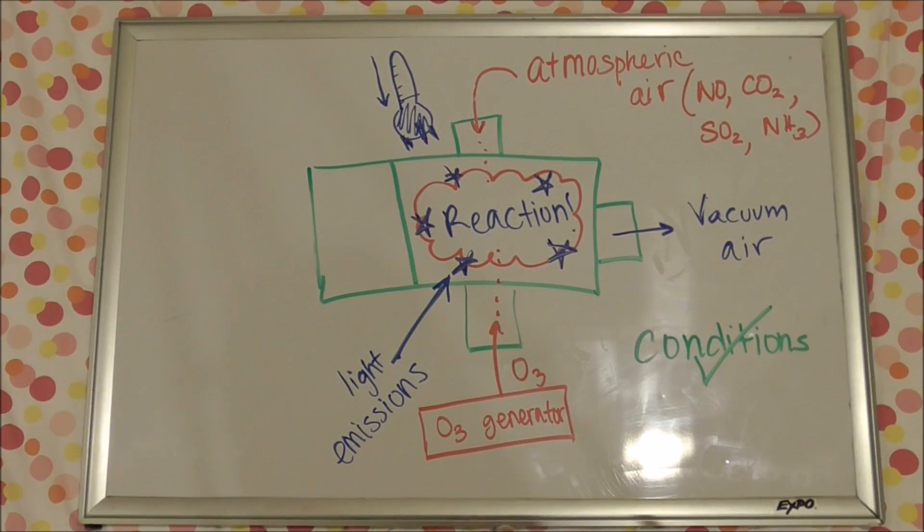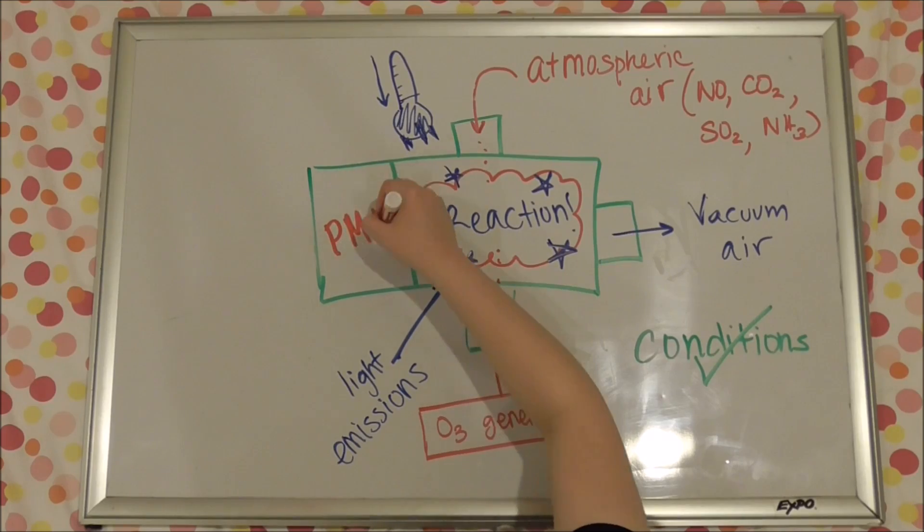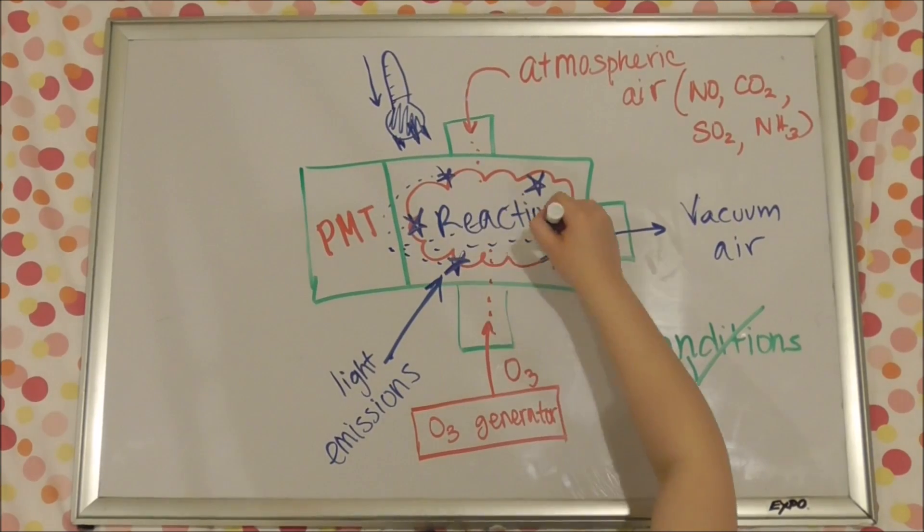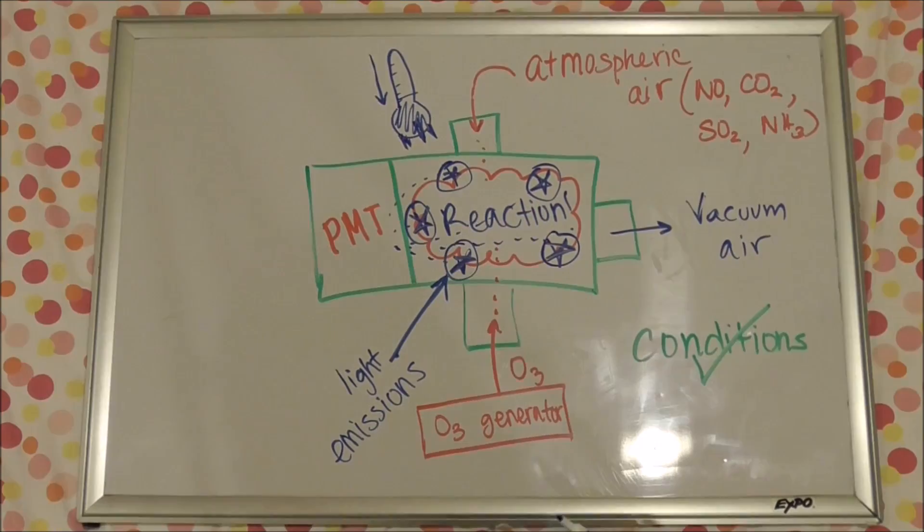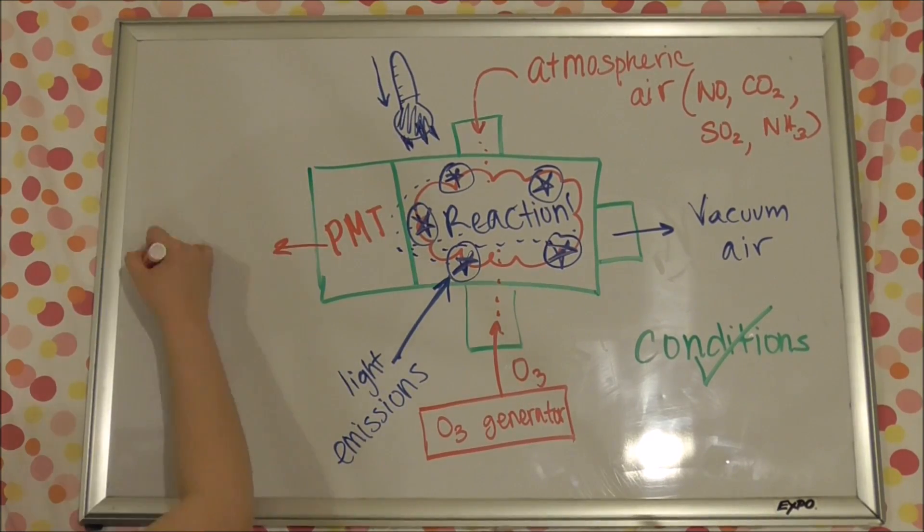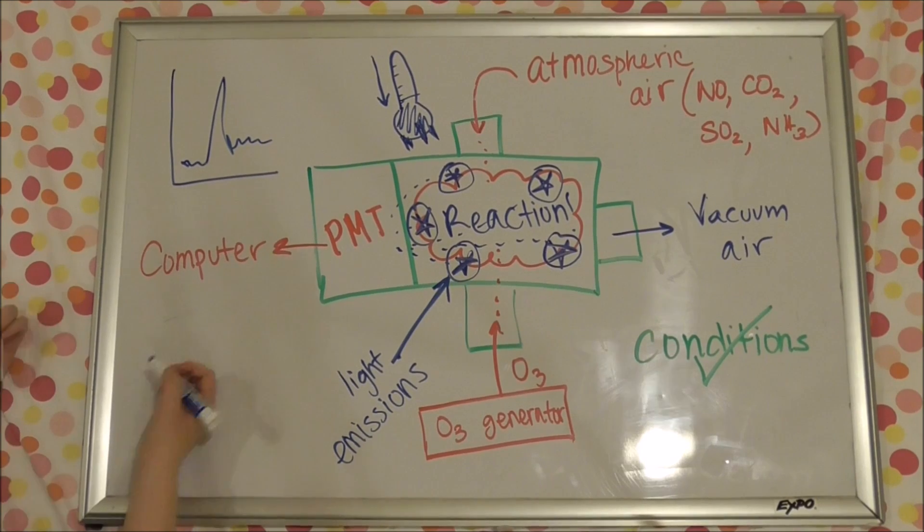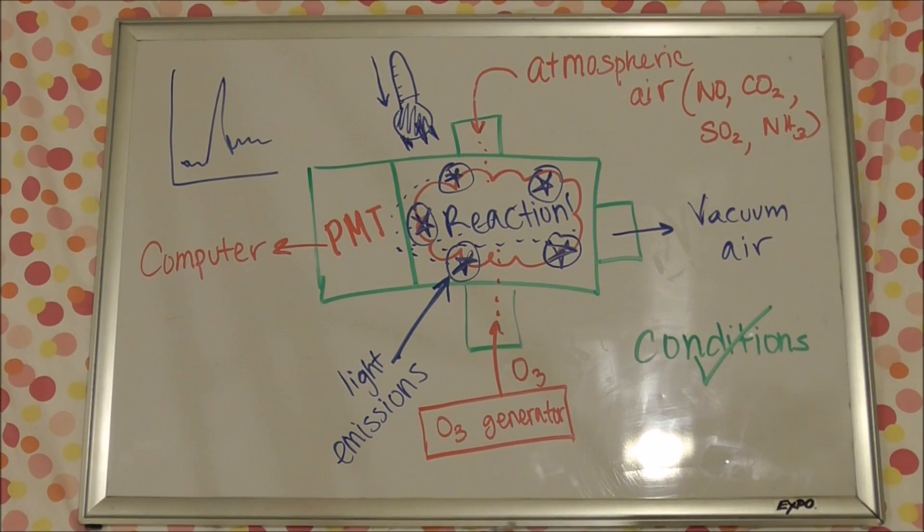Attached to the reaction chamber is something called a PMT, or photomultiplier tube. The PMT basically detects the light created by the reaction and feeds it into the computer system, which will create a graph that will show you the concentration of the NOx based on a relationship or equation previously inputted.